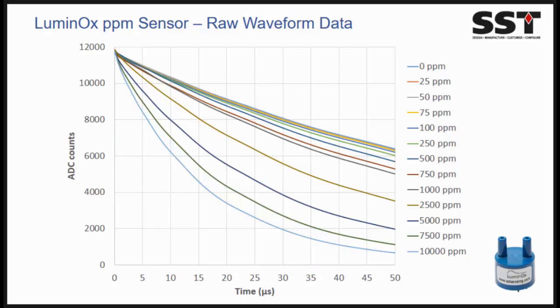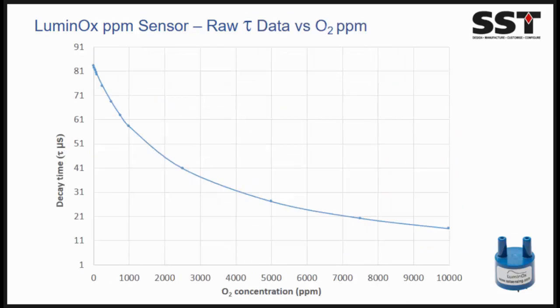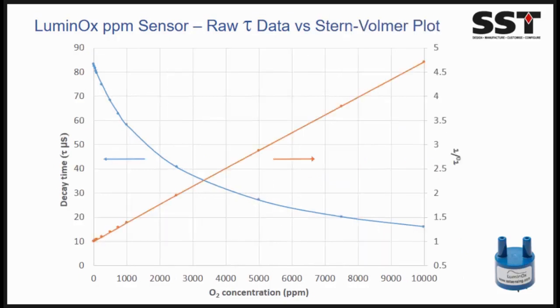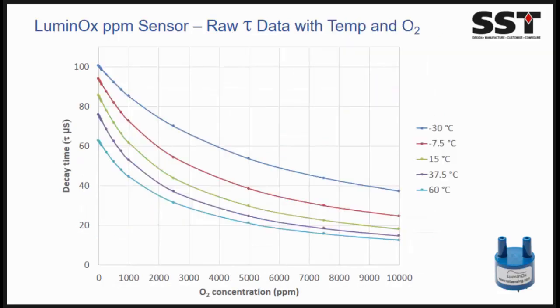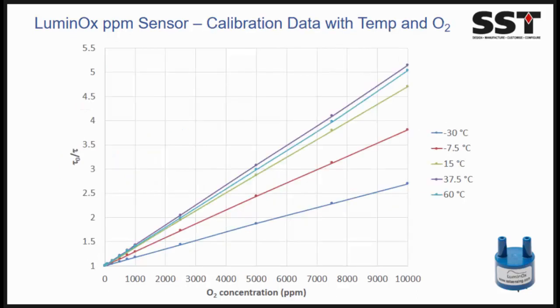So we've just gone up to 10,000 ppm in this case, which is 1% oxygen, but we will be looking to develop this sensor from 0 to 1000 ppm. So here, if you plot the raw decay versus PPO2, you get an exponential kind of curve. But if you do the Stern-Volmer, you will get a nice linear correlation. I mentioned temperature, so we are looking to characterize and develop this sensor from -30 Celsius to 60 Celsius. Again, you can clearly see that as you increase the oxygen and the temperature, the decay time will continuously drop. Again, if you plot the Stern-Volmer, you get a nice linear correlation.